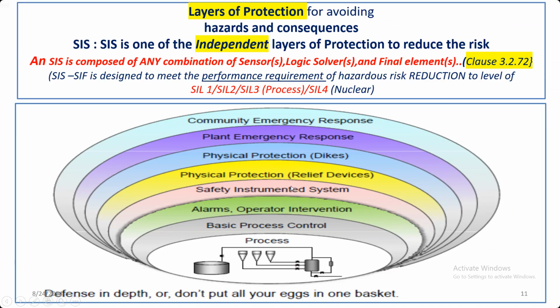So let me give an example of SIS. If SIS fails, we need a separate protection layer for the pressure. Say, for example, you have to maintain the pressure in the reaction or in the reactor or in the equipment at a safe level. If all three layers fail, that is, BPCS fails, operator intervention with alarm fails, and SIS fails, you have to install a process safety valve like in a boiler. The Indian government has a Boiler Act. Every boiler needs to install two safety relief valves. This is the fourth layer of protection.